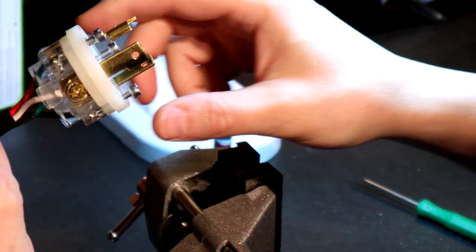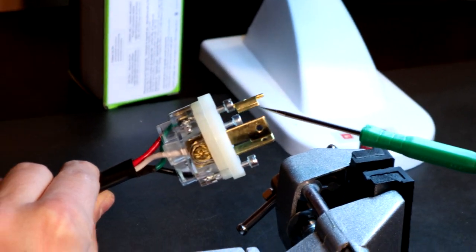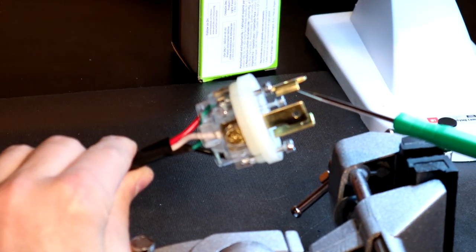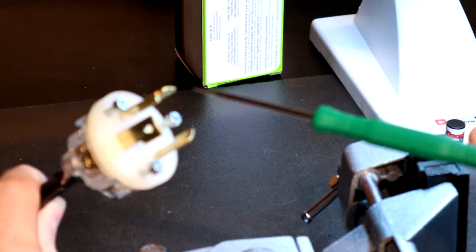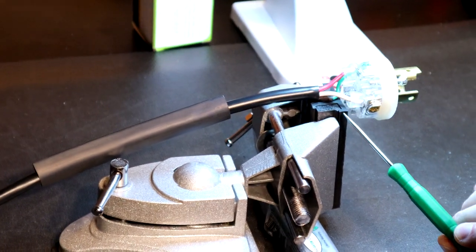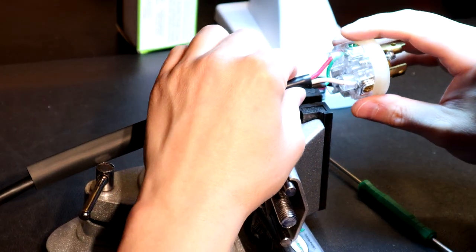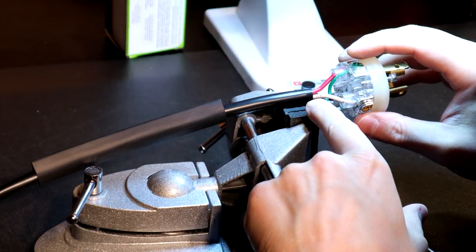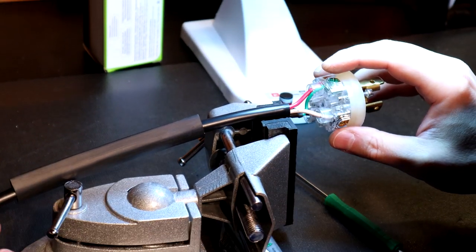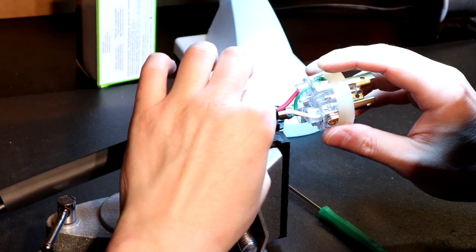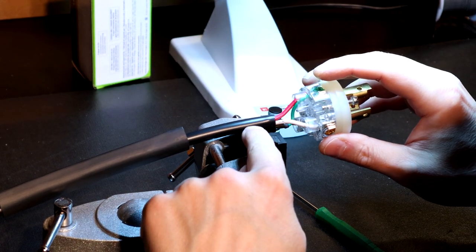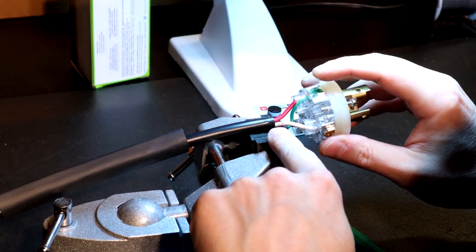What makes this connector also very unique is it's a screw and lock in place. You can see the ground here, how that terminal's got like a lip to it. That lip goes in and locks so that this connector will not move. So you can see how one of these is built. Your measuring needs to be done very carefully because if you overcut the cable, you'll find that you will not have enough meat on the actual cable for your stress relief. You do not want to cut this too far back.